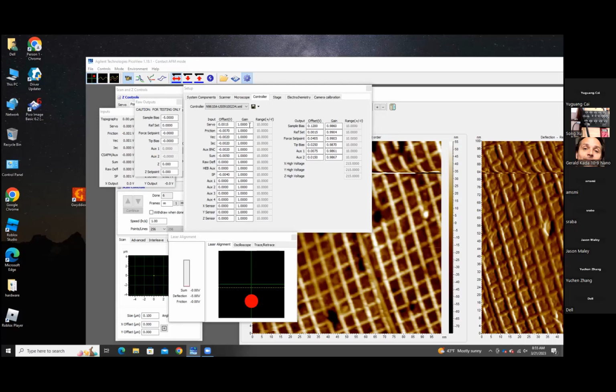You can simply do that by setting your 5 volt output on a calibrated output like a sample bias output and connecting a BNC cable from your sample bias to each of those inputs on your breakout box and see that they go to the proper value. And then you follow the same process on your gain. Take your known value, divide it by your measured value, multiply it by your gain value, and that will be your new gain for each of those outputs and inputs. And that's how you calibrate a controller.